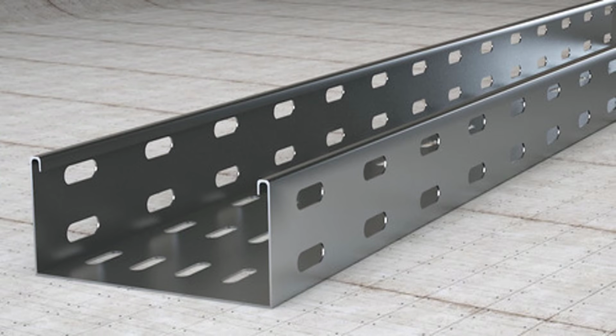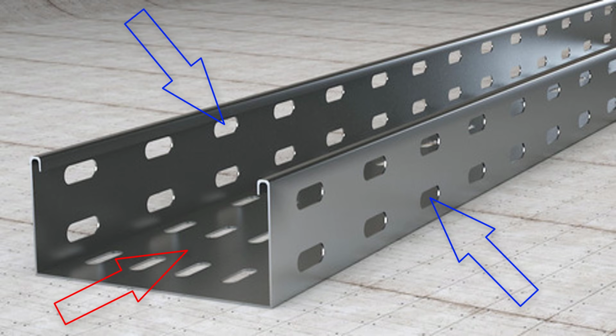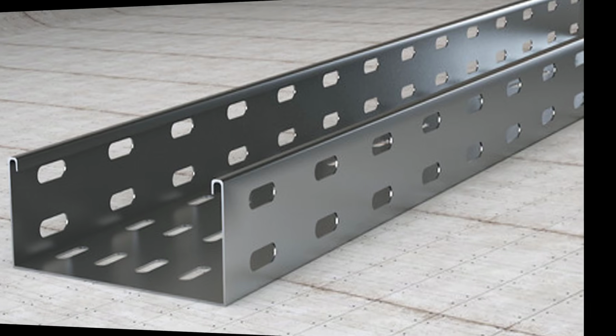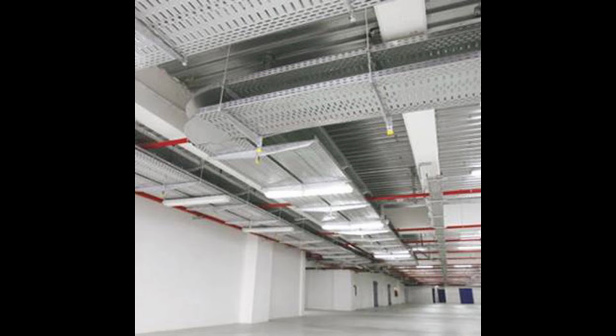The perforated type cable tray is called perforated because it's a ventilated tray from its bottom and both sides. This perforation allows air circulation for the cables, also allows some dust or water leakage above the tray to fall down and not to stay in the tray.